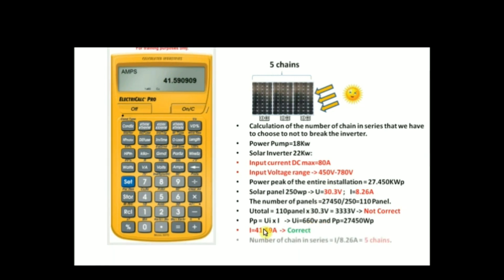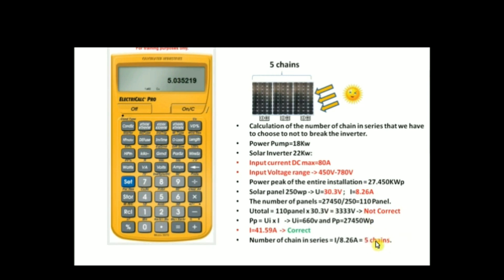To find the number of chains in series we need, we divide this current value by 8.26 amps, which is the current delivered by each individual panel. So we divide 41.59 amps by 8.26 amps, and as you can see, the result is 5. We're going to need five chains in series to respect the ranges of the solar inverter.